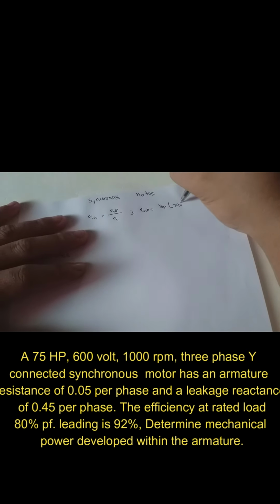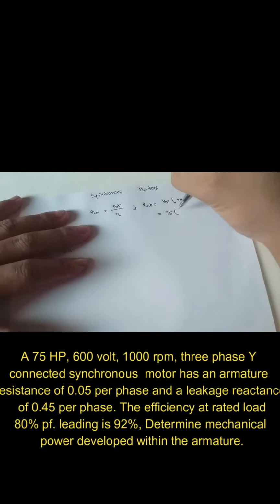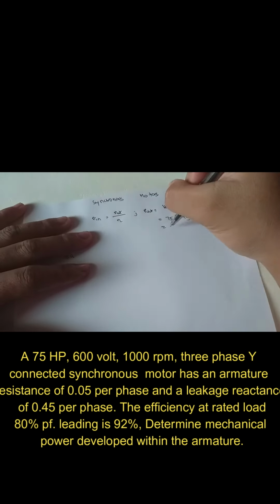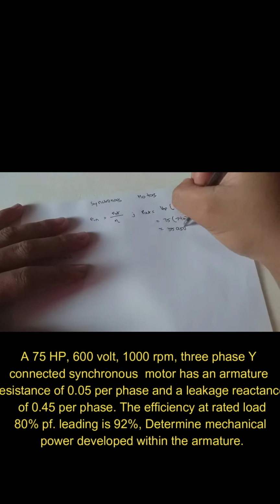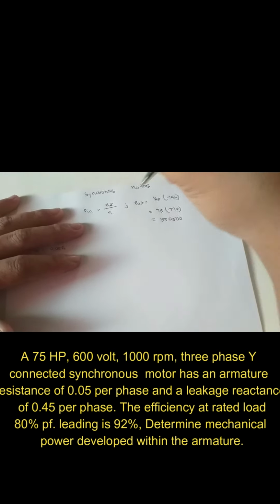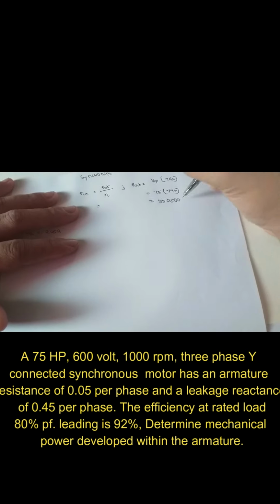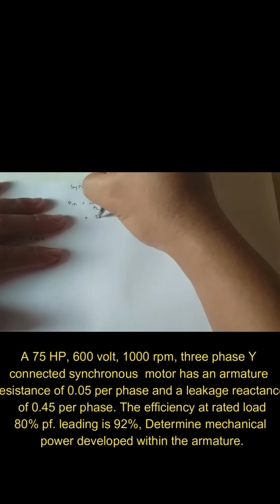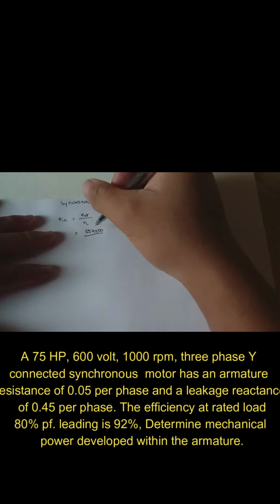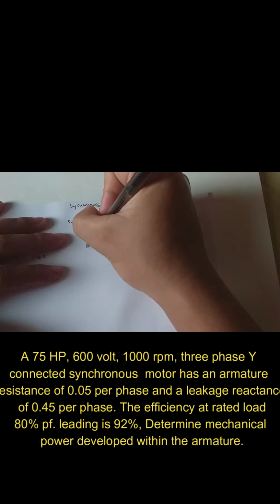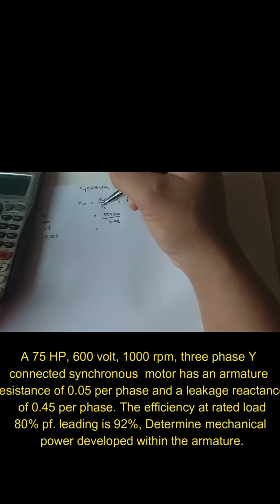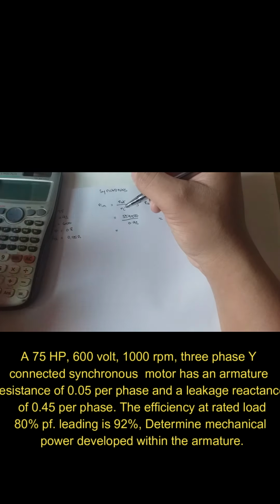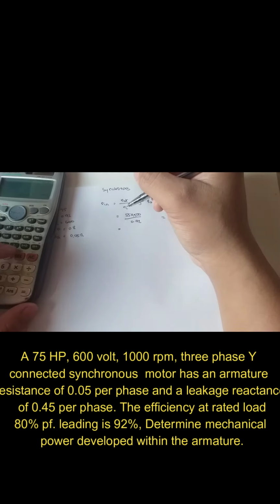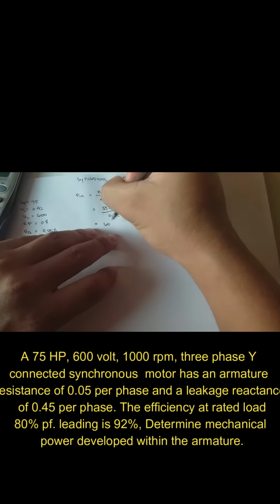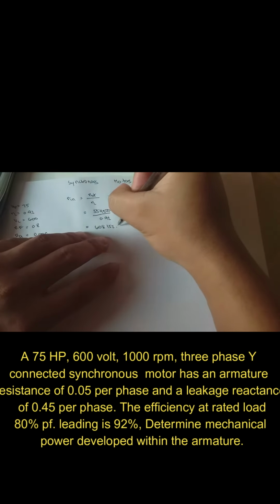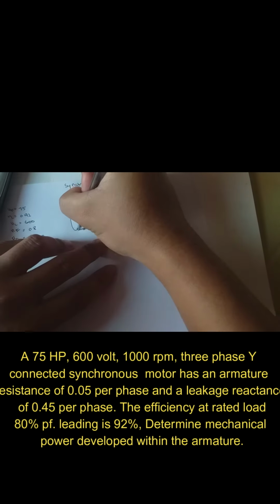Horsepower times 746, 75 times 746, 55,950 watts. So now we can compute the input power. 55,950 over 0.92 is 60,815.217 watts. That's our input power.